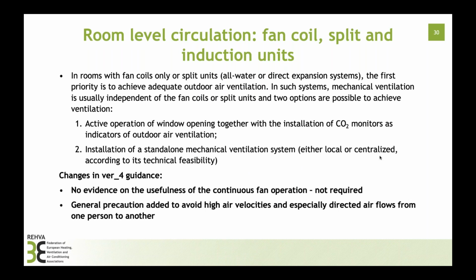Last year there was quite a lot of discussion about the situation with fan coils and split units, which just circulate a lot of air, and what will happen with the virus. Actually, these units also have some very coarse filters inside and basically very small filtration efficiency, but this is actually some positive effect, some still small removal effect. But the problem typically in rooms where fan coils or splits are applied is the outdoor air ventilation. It's important to check that there is enough outdoor air ventilation, where basically window opening is one way. So open the windows together with the cooling to ensure outdoor air ventilation, and then control this with a CO2 sensor. This is one option.